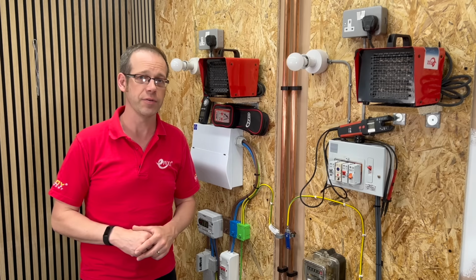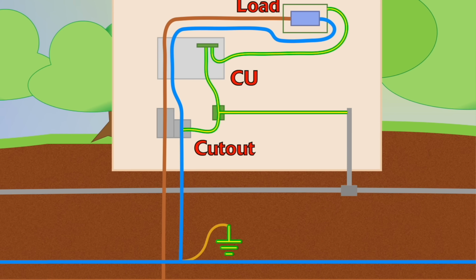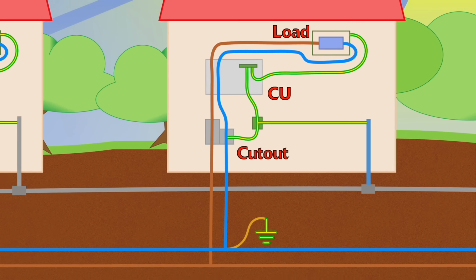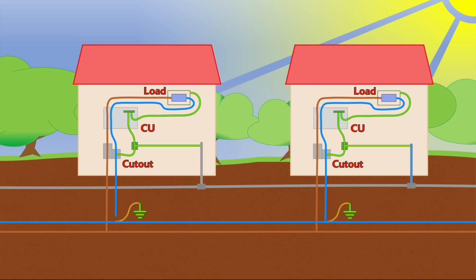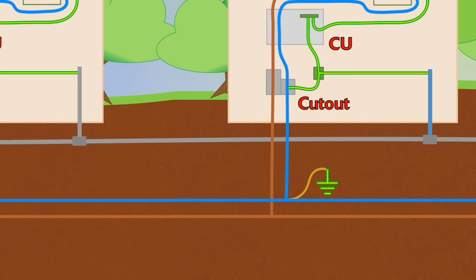Let's discuss scenario 2. Here we've got one slightly more modern property with a plastic incoming pipe and the older property still with its incoming metal water pipe. If the same fault occurs, then we've got a PEN fault, which is a problem, but there's no neutral current being diverted from a different property. A larger problem would occur if we lost the neutral here.